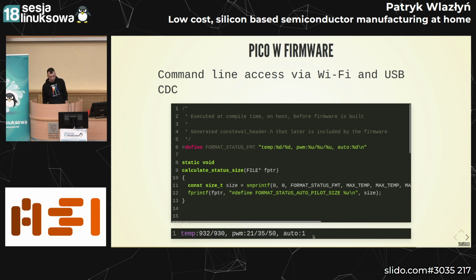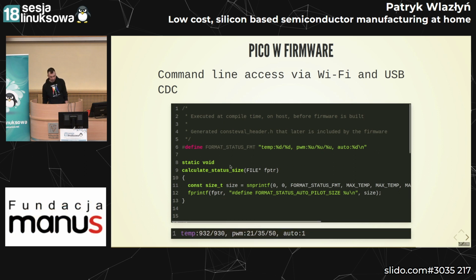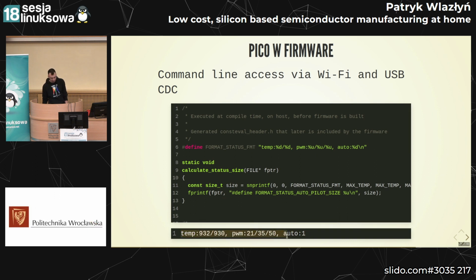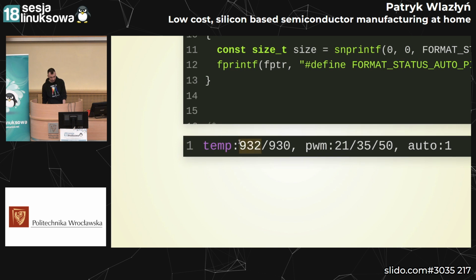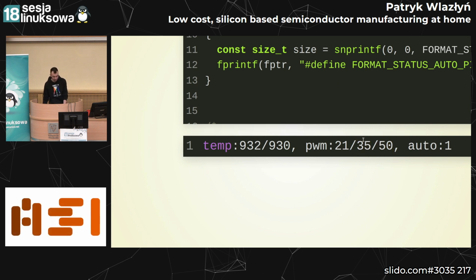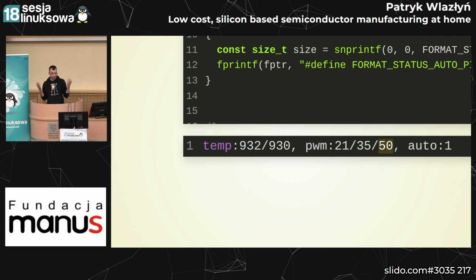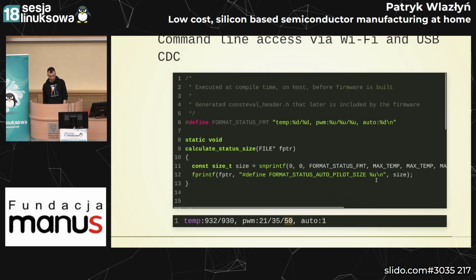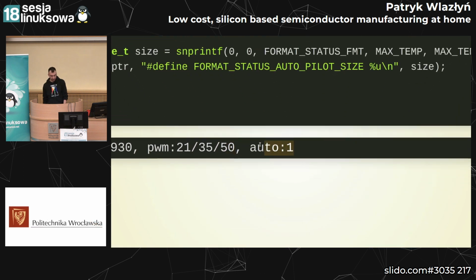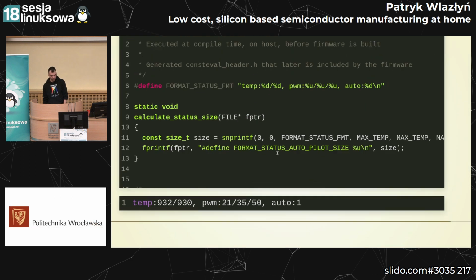This is the example of the status line at the bottom. We have a current temperature, 932 degrees, out of 930 requested as the desired temperature. Right now we're sitting at 21 PWM level, with a max of 35 and total max of 50. This 35 is actually settable at runtime - it's the absolute maximum PWM value, and we're sitting at auto steering of the furnace.